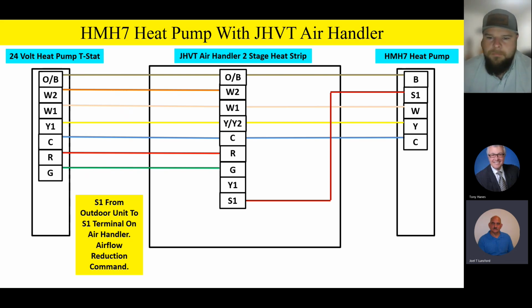We've got to set the control board up to look at the S1 input. That's a little step you have to do in the install guide to set the board up to look for S1. And then you take that S1 wire from the outdoor unit right to the board on the JHVT air handler. So once you get all that set up, you've eliminated that relay kit altogether, but the contractor still has to provide that liquid line bi-flow filter dryer.